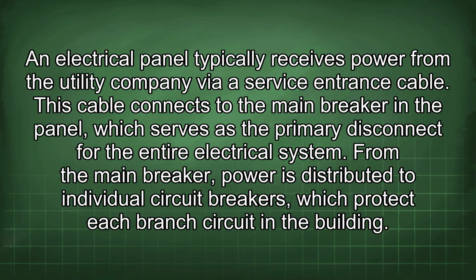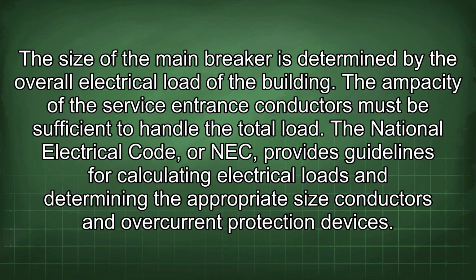An electrical panel typically receives power from the utility company via service entrance cable. This cable connects to the main breaker in the panel, which serves as the primary disconnect for the entire electrical system. From the main breaker, power is distributed to individual circuit breakers which protect each branch circuit in the building. The size of the main breaker is determined by the overall electrical load of the building. The ampacity of the service entrance conductors must be sufficient to handle the total load.